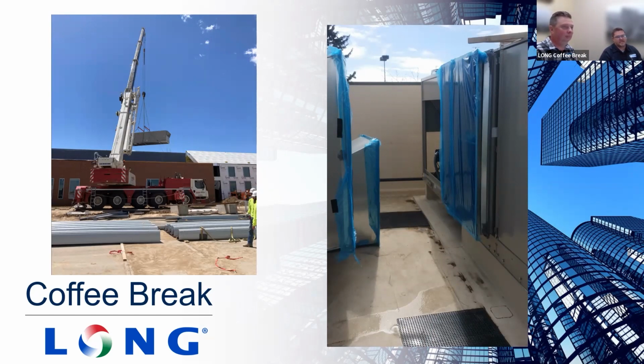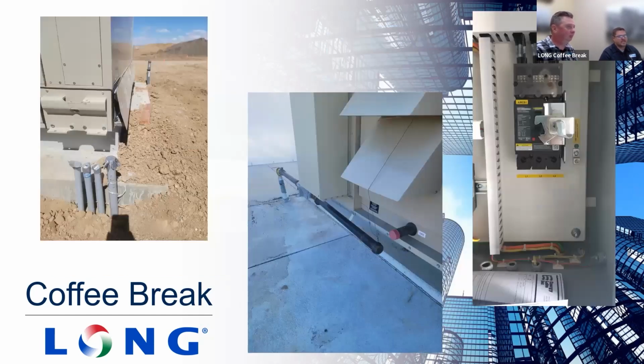And the next picture is one that shows the ductwork not complete. The transition's not installed. It's laying there on the job. It's ready to go, but it's not there. So it's not the most ideal condition to try to start this piece of equipment. Exactly. This example here is of line voltage and control wiring conduit penetrating through the ground with nothing in it. But of course, without power, we can't run the machine.